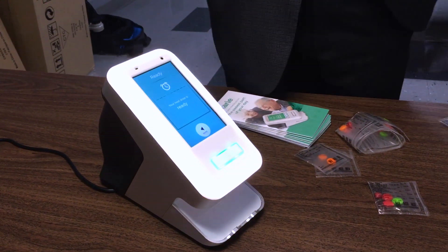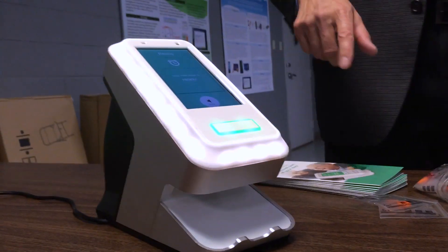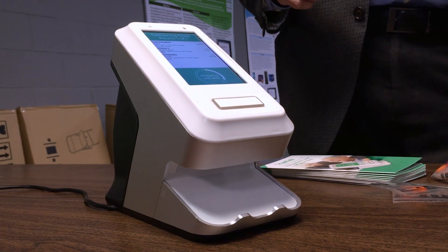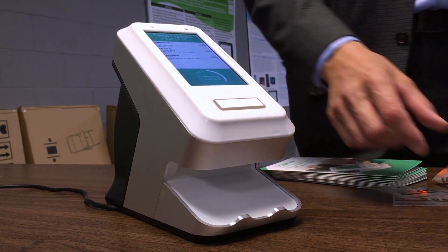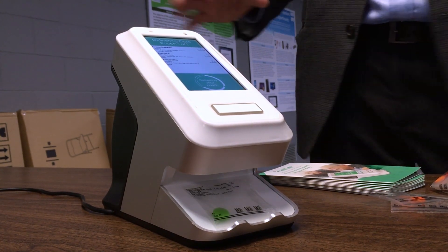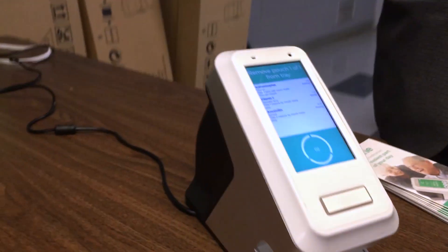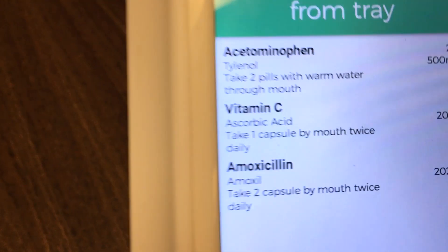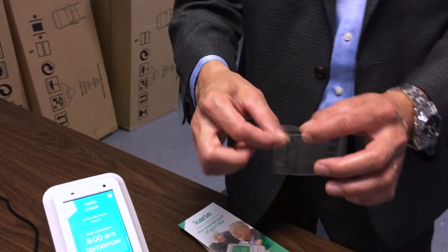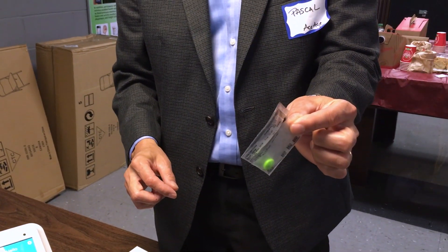it will alarm and you'll get a light, you'll get a sound — which you might not hear because it's quite loud in this room — and all you have to do is press the one big button in order to deliver the pouch of medication that will look like this. Essentially what the Karie unit is doing now is validating that the medication is to be delivered at this time, severing it from the strip, and also putting in a little nick so that it's easy to open for people with arthritic fingers.